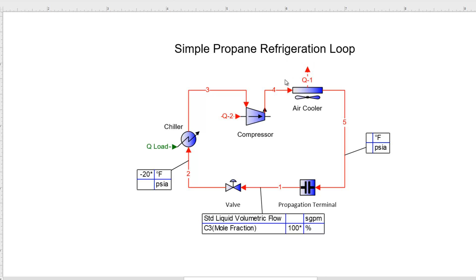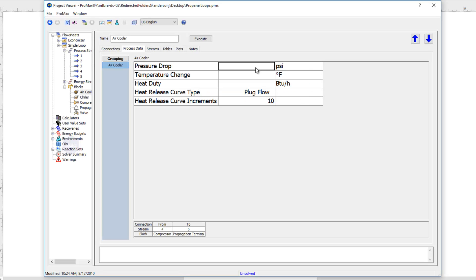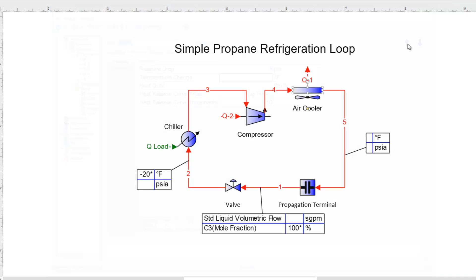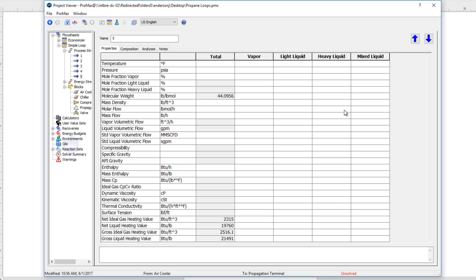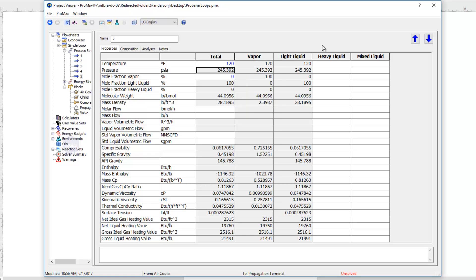I could come into stream 4 and type a pressure in directly, or I could just tell Promax that I want 100% liquid coming out of my air cooler at my air cooler temperature, and Promax will calculate the pressure that my compressor will need. I'll first open up the air cooler and give it a pressure drop — 5 pounds. Then in stream 5, I'll tell Promax my air cooler temperature is 120 degrees and that I should be 0% vapor at that point. You can see in the pressure row that Promax has calculated the pressure needed to be 0% vapor.